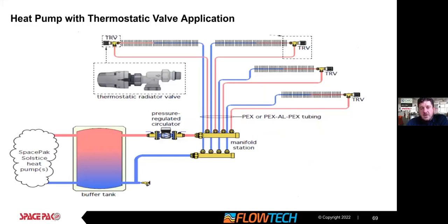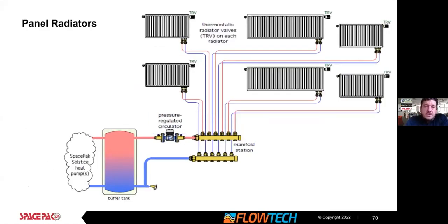I wanted to show, this is back to our applications, how well suited the SpacePak is for different applications, and we'll go through some of those right now. I always like to think of it like there's a big line right through that buffer tank, everything on the SpacePak side and then everything on the system side. And nothing really changes on the system side just because you're using a heat pump. It's basic hydronics. We're feeding right here, radiator valves on here, baseboard stuff with the manifold set up. Here we're showing it being pulled into panel radiators, and through manifold setup as well. So any of your distribution methods we talked about, these are some examples of how nothing really changes just because you're using a heat pump.